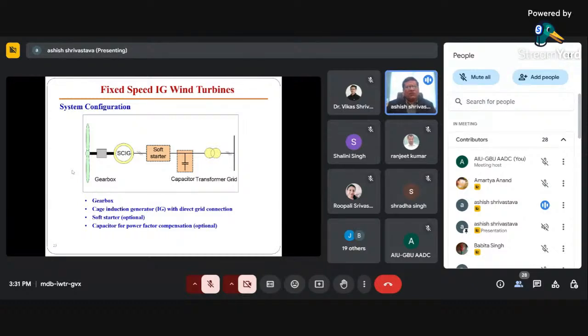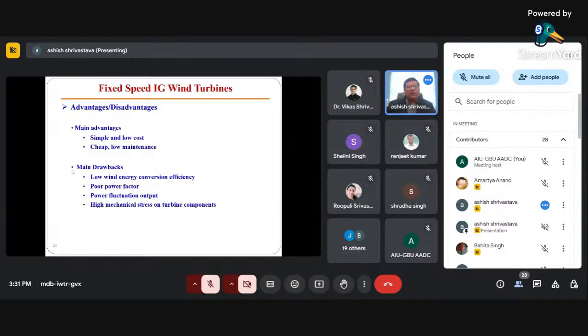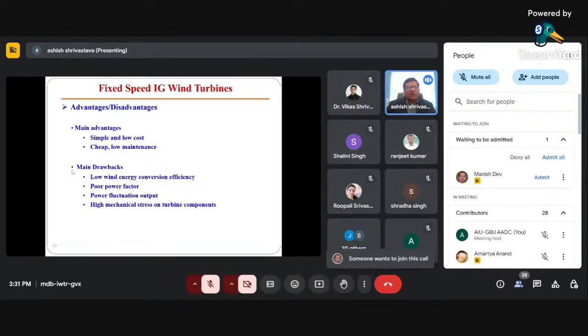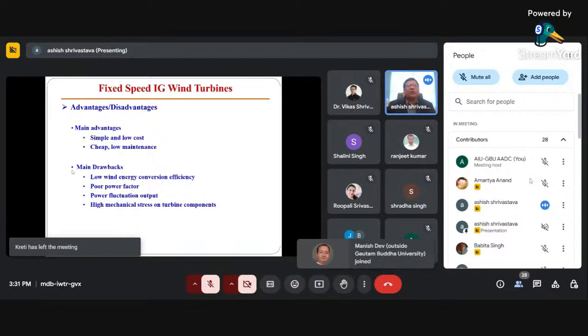So in this system, we have a gearbox and a cage induction generator with direct grid connection. Then we have a soft starter and then a capacitor for power factor compensation, or reactive power compensation. For the fixed speed induction generator, there are certain advantages and disadvantages. If we talk about the advantages, it is simple and cost effective. Maintenance-wise it is also quite low, but there are certain drawbacks.